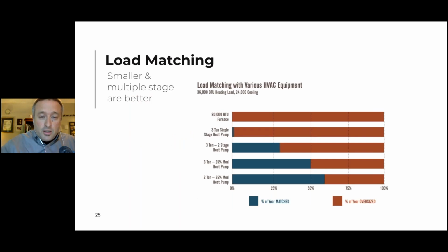Now, what this looks like in practice with actual HVAC equipment, this is kind of a typical house here that we find in Cleveland, which will shock most people, because the smallest furnace that you normally will see is 60,000 BTUs, where a standard air conditioner or heat pump is 36,000, or it's also known as 3 tons. Every ton is 12,000 BTUs. So very commonly, we will walk into a 2,000 square foot house and it will have an 80,000 BTU furnace. That is the wrong size equipment all of the year.